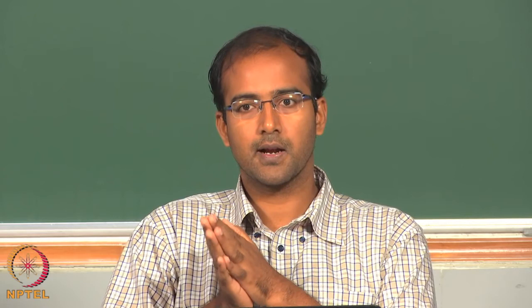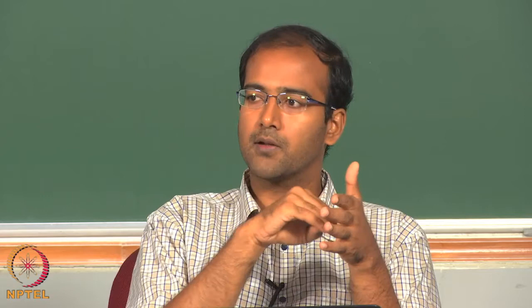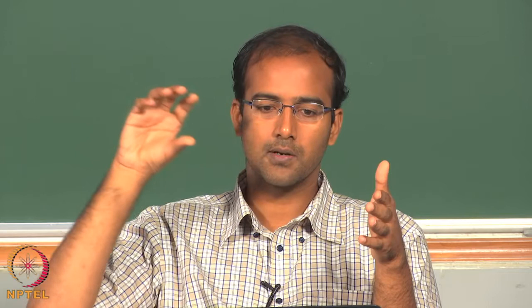The heat generation happens at nanometers; level 1 dissipation to the chip carrier is mostly governed by contact resistance — a material phenomenon. From the substrate, which is of the order of millimeter square, micro channels can be etched in parallel into the substrate to make transfer of heat to a cold plate outside much easier. From the cold plate, conventional techniques such as heat pipes, fans, or impingement cooling handle macro-scale heat removal.